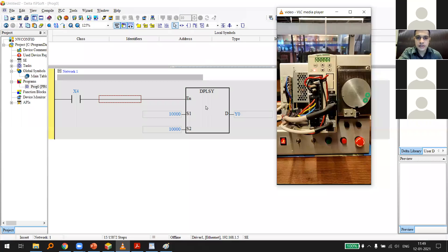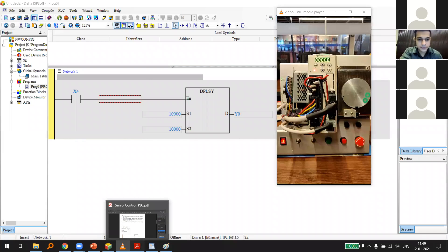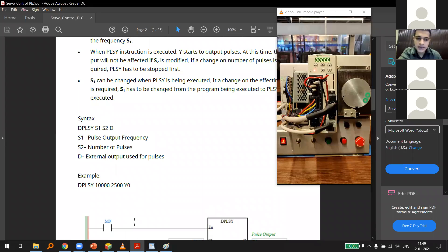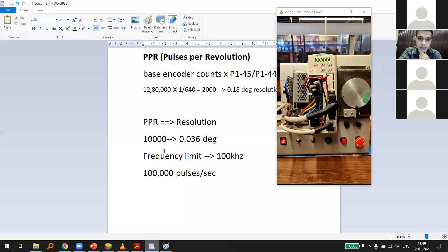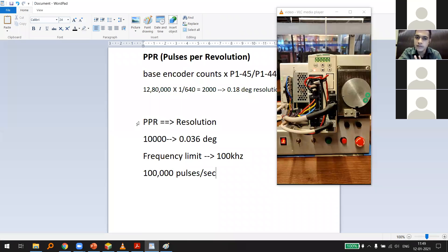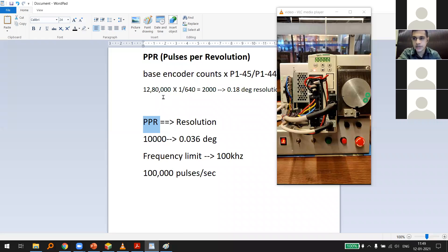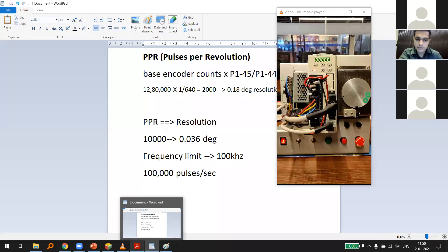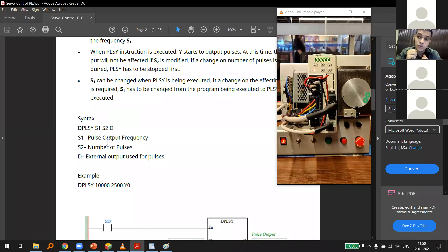In programming: S1 is the pulse output frequency — that's your speed. S2 is the number of pulses — that's your position. Number of pulses directly corresponds to PPR: a PPR of 2,000 means giving 2,000 pulses rotates the servo one full revolution. Speed is expressed in pulses per second or degrees per second.